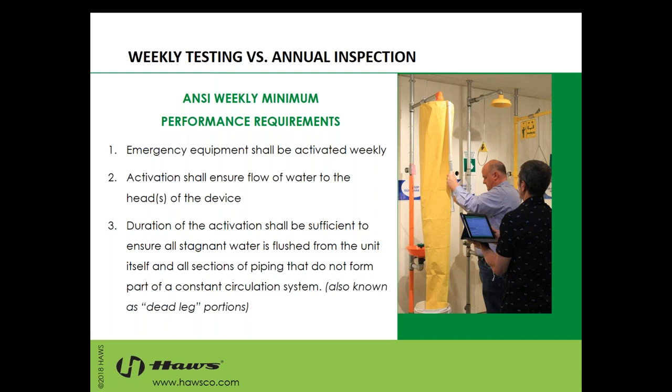And if you don't know what a dead leg is, there is a portion of piping between the emergency equipment and the source of water that is static. It's not moving. So we need to make sure we flush that water out and get new water in there so we don't have any growth in the pipes.